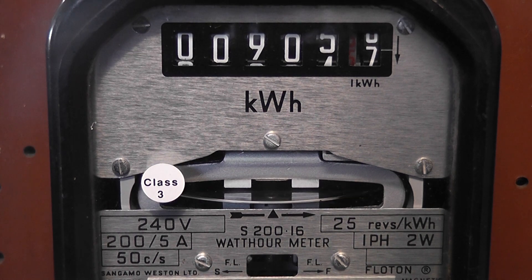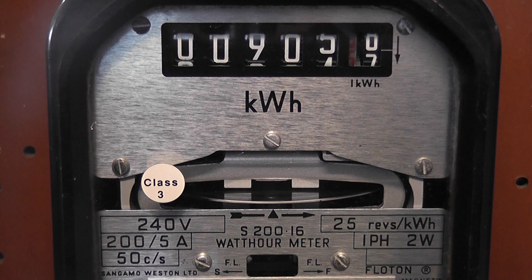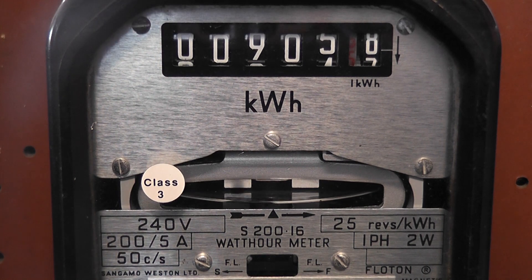Thanks mate — more videos to come of these special meters, but I'll have this one up as a little appetizer. It's simply brilliant. The meter is running at 8 ampere at the moment, a bit overloaded, but a 5-amp meter will take 10 amps anyway. Now it's on 4.8 ampere and we'll flick it back up to the higher reading.